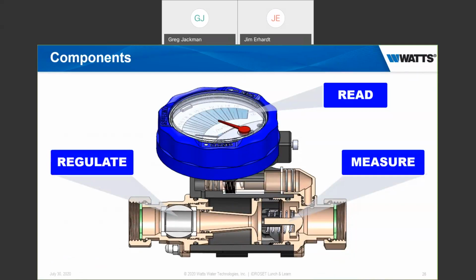So basically, it regulates, meaning that we have a ball valve in there that is directly mechanically controlled by the blue handle. The flow rate is read by the gauge itself; there's no water flowing through it, and it's not mechanically connected to the valve. Rather, inside the valve in that upper chamber where we're reading the flow, there's a magnet, and the magnet moves the needle in the gauge. So, one of the questions we had was, what happens if the gauge fills with water? It's not connected. It's not in the water path. The needle is moved by that magnet. And it measures the flow rate.